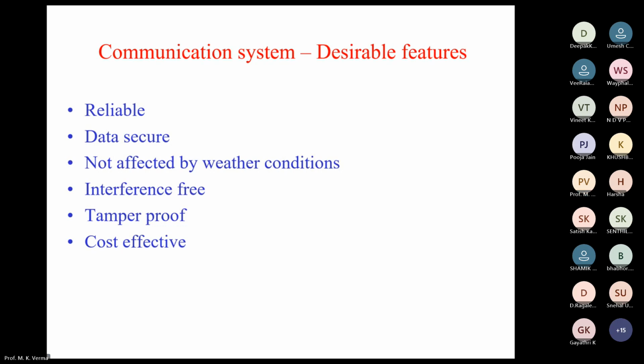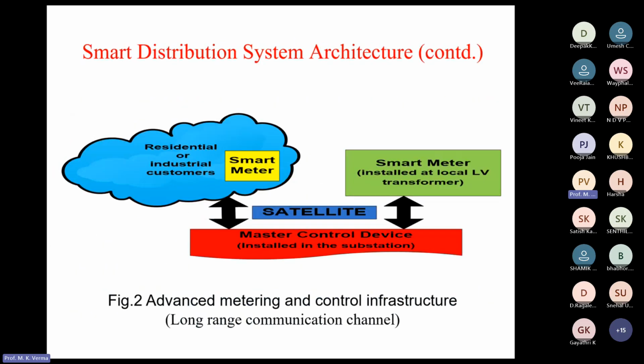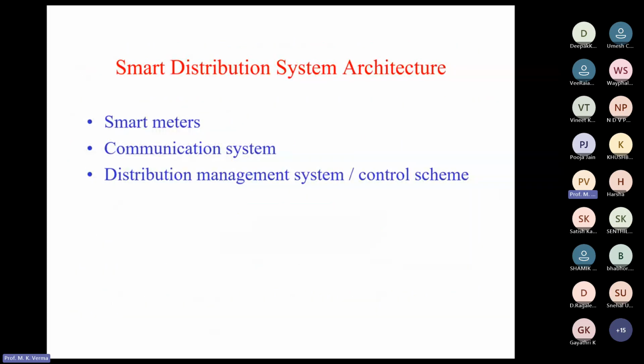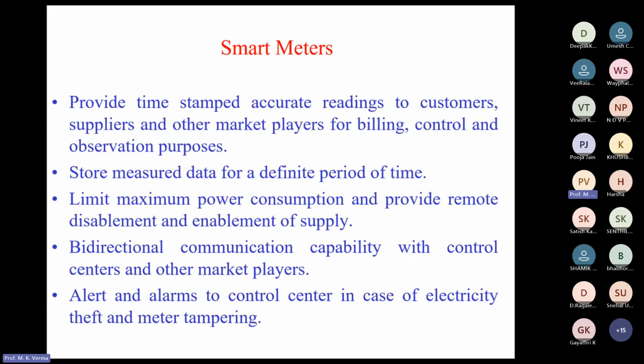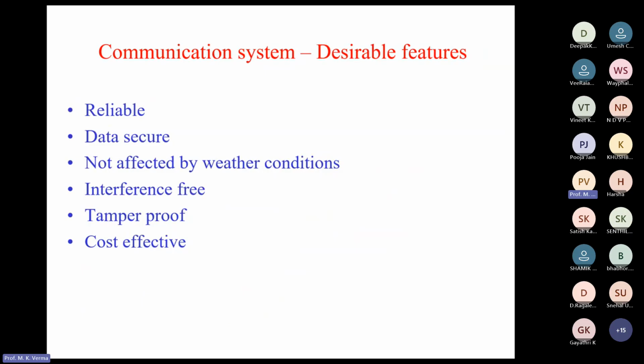Communication system. The first component is the smart meter, then the communication system, and then the third component, the distribution management system. I talked about smart meters. Next, the communication system. The features of communication systems are that they are to be reliable. The data is to be secure. It should not be affected by weather conditions, and it should be interference-free, tamper-proof, and cost-effective. It should also be robust against cyber attacks. Some cyber security should also be provided for this communication media.